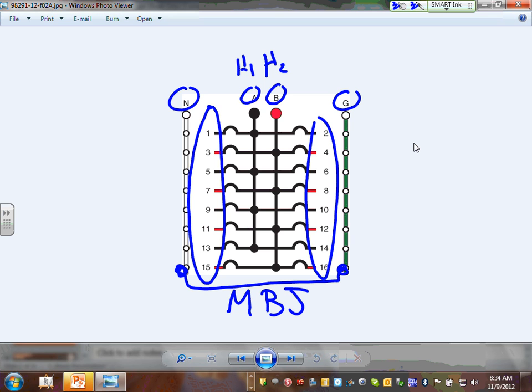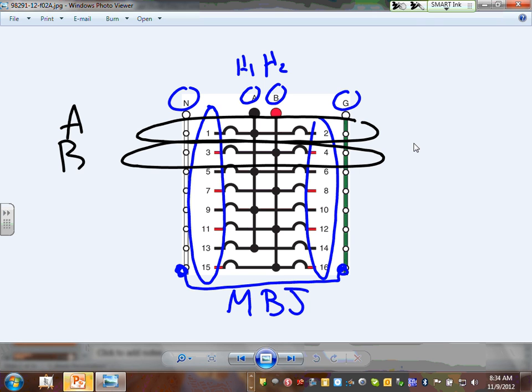The second thing, can you guys see that the ones opposite to each other are on phase A. The ones underneath them immediately are on phase B. Can you guys see that? Everybody can see that? Every two circuit breakers opposite to each other are on the same phase. Thumbs up, Chad. We understand? Every two circuit breakers next to each other are on phase A and B. Right? That's how you get to 240. Everybody understand this? Please don't graduate from here not knowing this. That's what I want to highlight. Everybody understand that? So we have a neutral, we have a phase, and we have hot 1, hot 2.